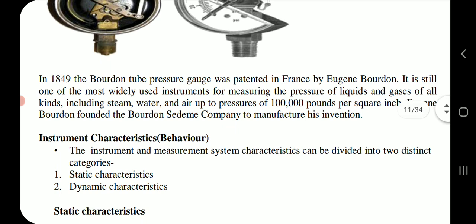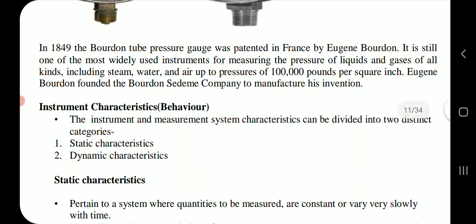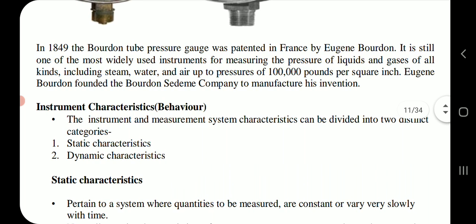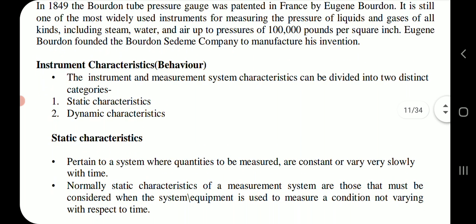In 1849, the Bourdon tube pressure gauge was patented in France by Eugene Bourdon. It is still one of the most widely used instruments for measuring the pressure of liquids and gases of all kinds, including steam, water, and air, up to pressures of 100,000 pounds per square inch. Eugene Bourdon founded the Bourdon Sedeme Company to manufacture this invention.